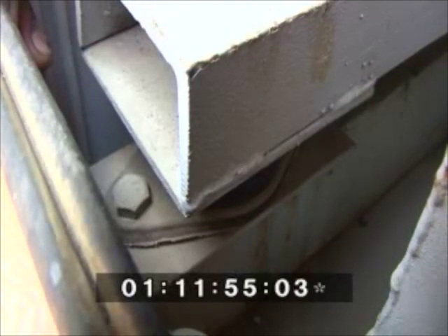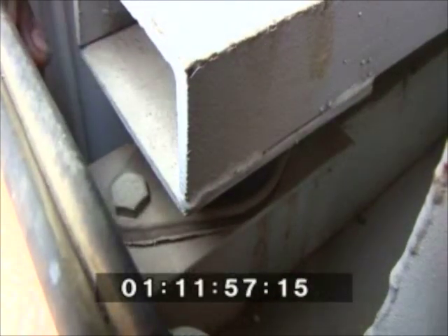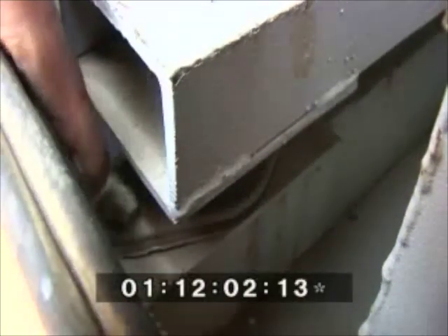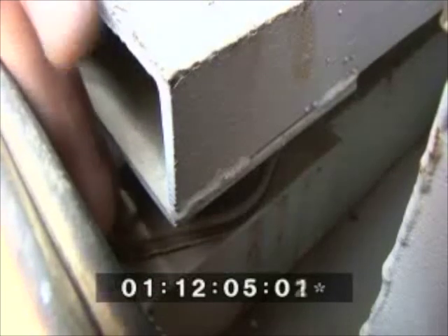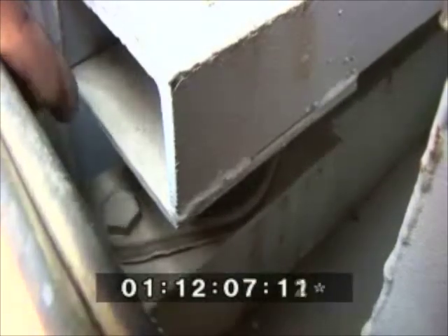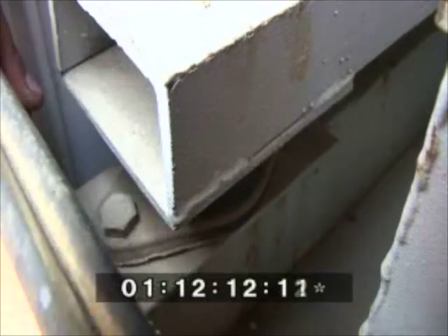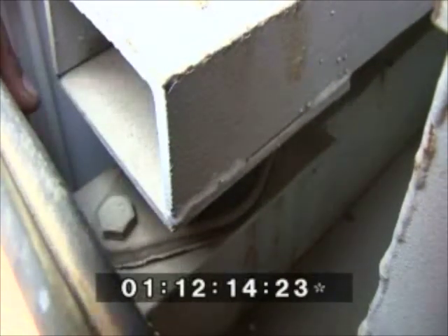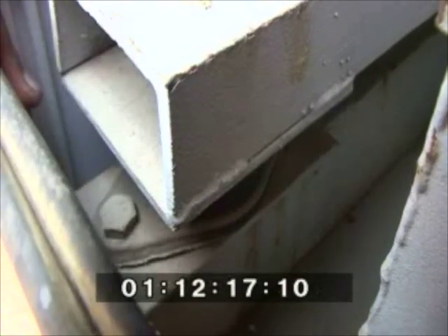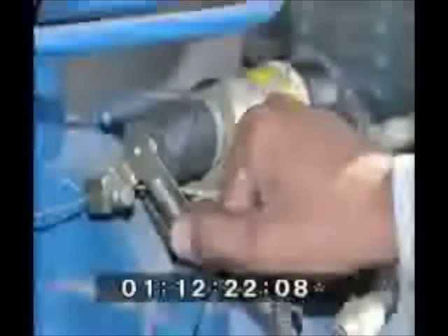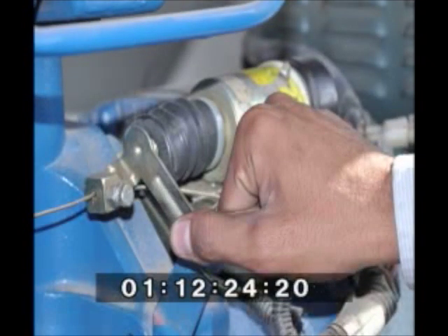The nuts in the DG would become loose and cracks can develop on the DG, creating damage to the DG, and there is possibility of accidents. We need to check the condition of AVM pad and check whether the nuts at the base of DG are tight or not. Now we shall do the stop solenoid check.